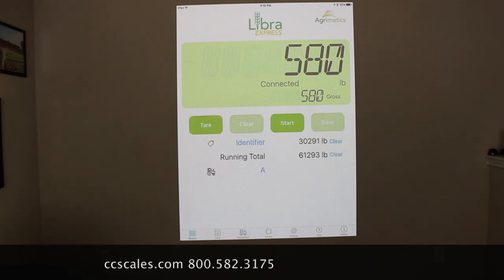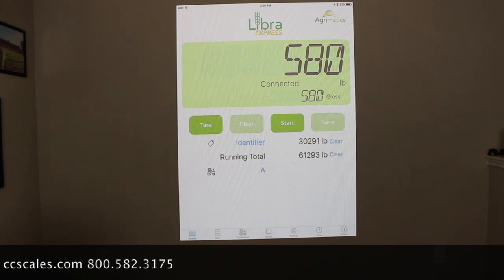Okay, I'll hit save, and then I'll take that load to a certified scale and make sure that it reads out at 30,300 or so. So 30,291 would be the exact, and then verify based off of that point for your calibration.